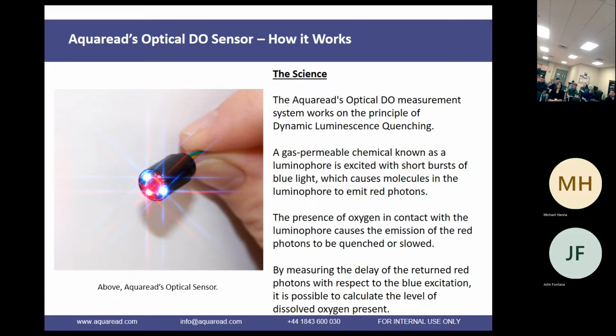So you can see on here, the LEDs are flashing away. When you're using the sensor, that's what's happening. These LEDs are constantly beaming into this membrane, which has the luminophore inside, and they're taking readings all the time. The reading process of the sensor takes 11 milliseconds. So that's how fast our sensor is.